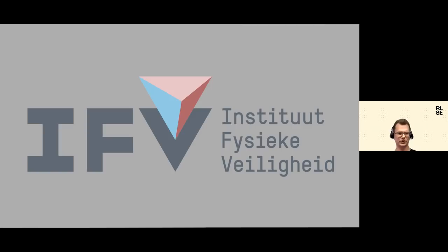So we have one live module in the middle, the rest are dummy modules. For this particular method, it's a bit different than say UL9540. What we're looking at here is specifically to compare how different fire suppression system setups, or different fire suppression agents, can be effective in hindering thermal runaway propagation. So it's a different kind of way that we're looking at things in these particular tests.